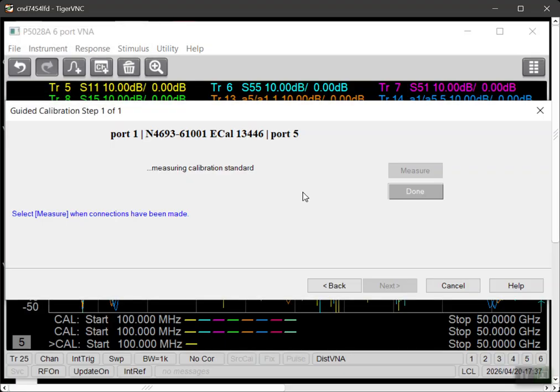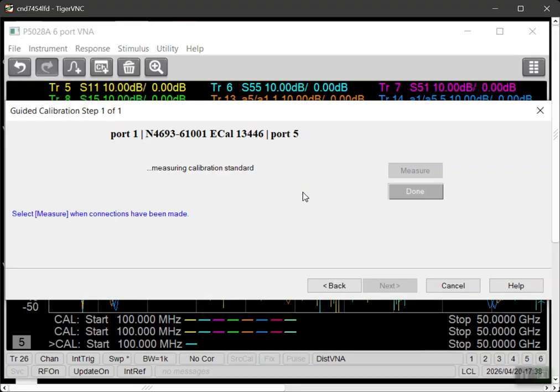My calibration here is 100 megahertz to 50 gigahertz. I'm running it at a 1 kilohertz IF bandwidth, and I have a lot of points. I have about 1,000 points because I wanted a 50 megahertz tone spacing just to have very good frequency resolution. So that's why it's taking a while to get through this calibration, because it's a lot of points at a 1 kilohertz IF bandwidth. But it'll be done any minute.